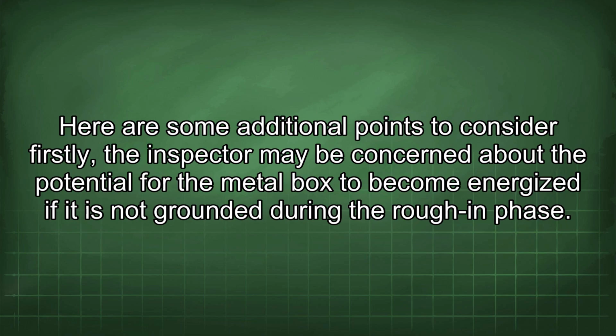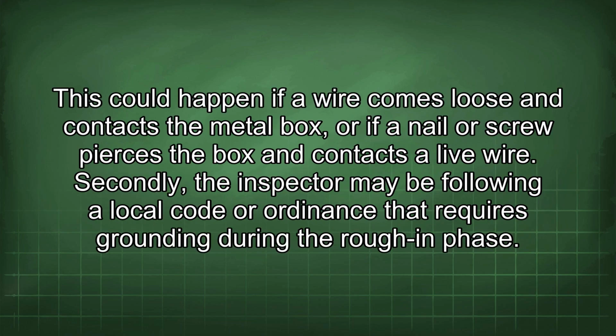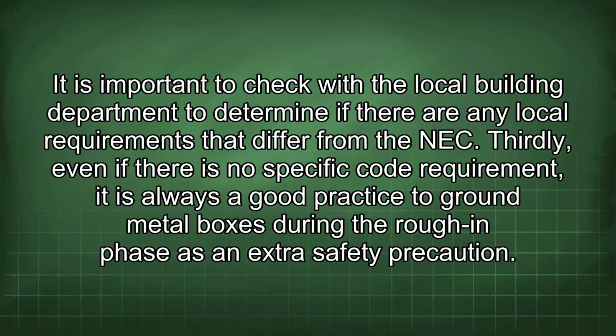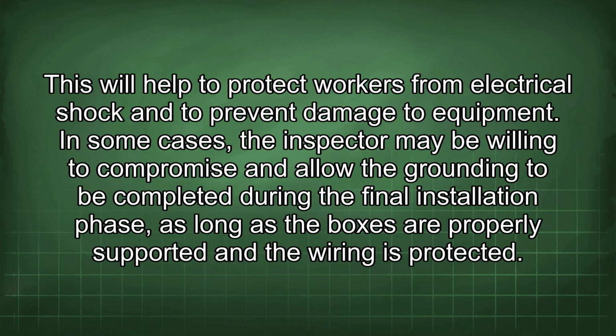Here are some additional points to consider. Firstly, the inspector may be concerned about the potential for the metal box to become energized if it is not grounded during the rough-in phase. This could happen if a wire comes loose and contacts the metal box, or if a nail or screw pierces the box and contacts a live wire. Secondly, the inspector may be following a local code or ordinance that requires grounding during the rough-in phase. It is important to check with the local building department to determine if there are any local requirements that differ from the NEC. Thirdly, even if there is no specific code requirement, it is always a good practice to ground metal boxes during the rough-in phase as an extra safety precaution. This will help to protect workers from electrical shock and to prevent damage to equipment.